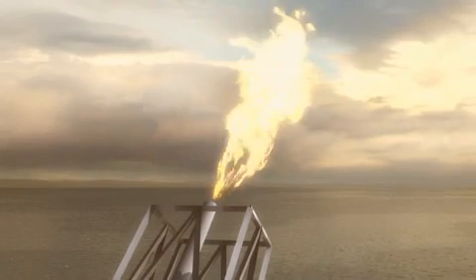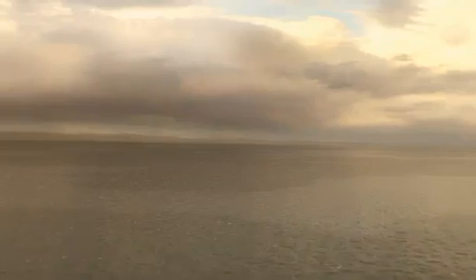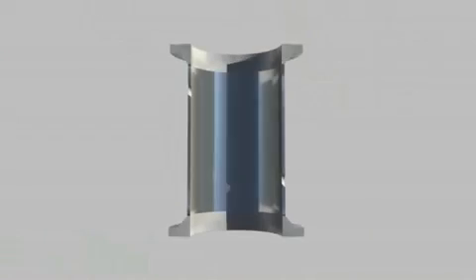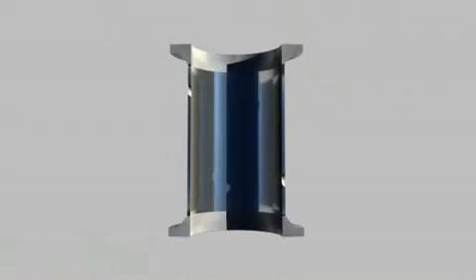The Fluenta flare gas meter system consists of a pair of transducers and a field computer with a maximum distance of 10 meters from the transducers. The meter is delivered with either a prefabricated spool piece or with lateral flanges, which can be hot or cold tapped to an existing flare line.